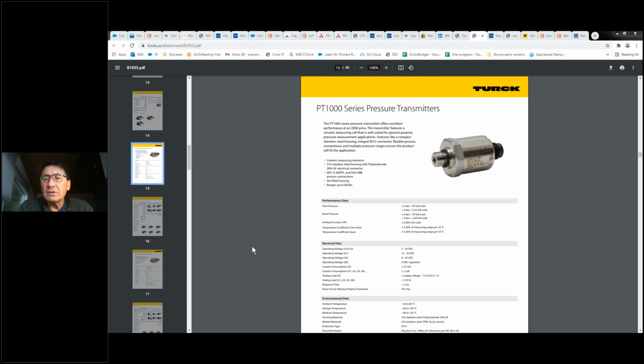That means by definition you're going to have flying leads. And you can buy the sensors and their over-molded connectors with flying leads out to 45 feet. We don't really want to make splices on signal cables. The cost of the cutaway wire versus the cost of basically the field time to install the field wiring, I think you're going to come out ahead buying the sensor with the 45 feet of cable. That adds about, I think, $6-7 to the cost of the over-molded head that connects to the sensor, and I don't think you're going to be able to field wire for $10-12 worth of labor. So, notwithstanding the reduced risk.